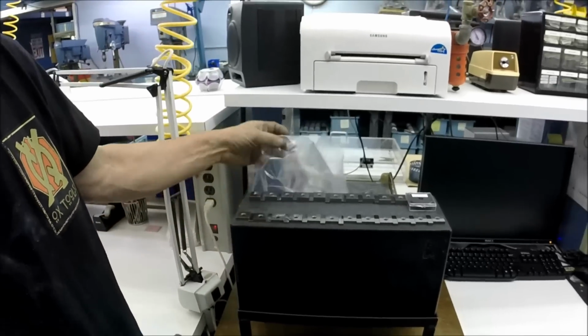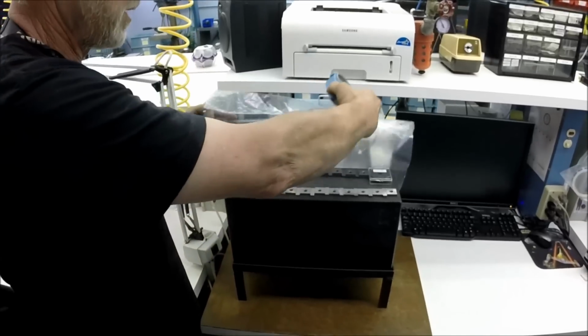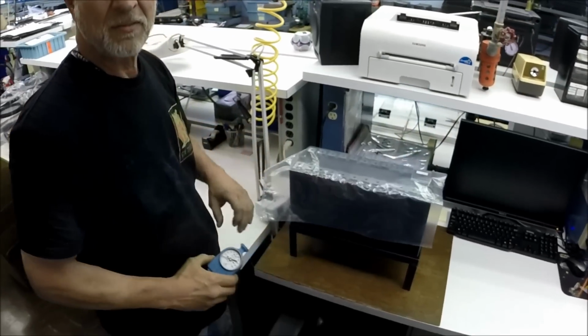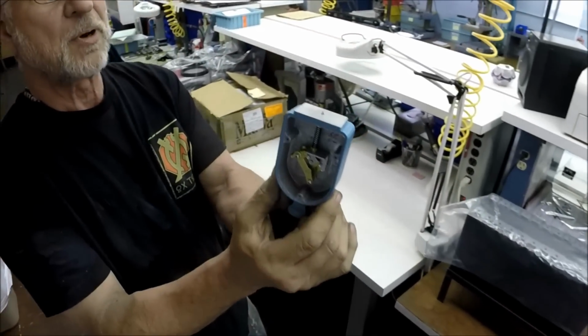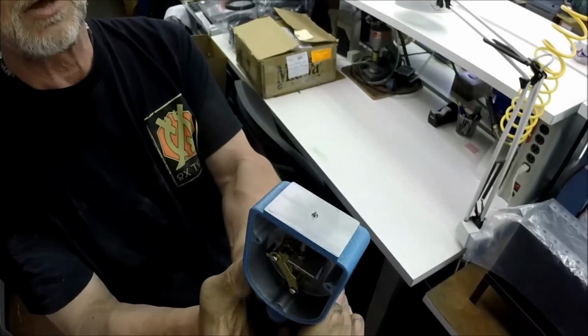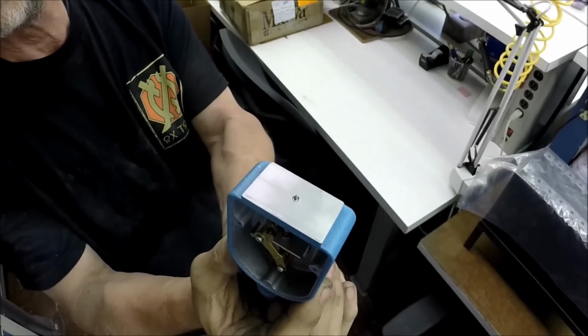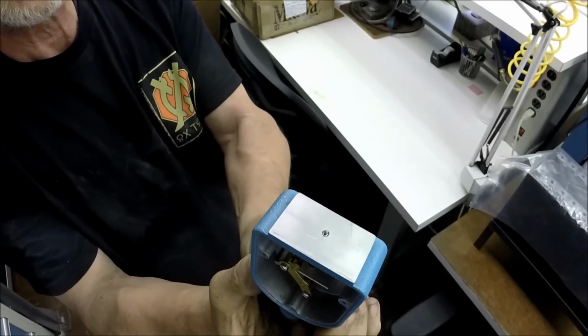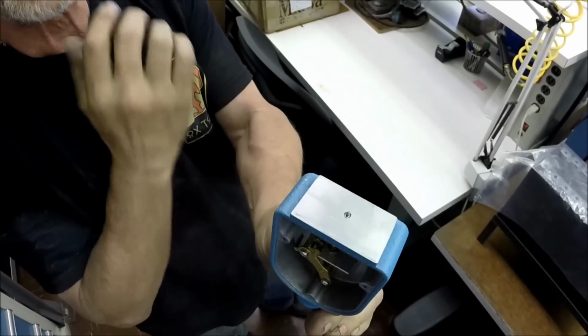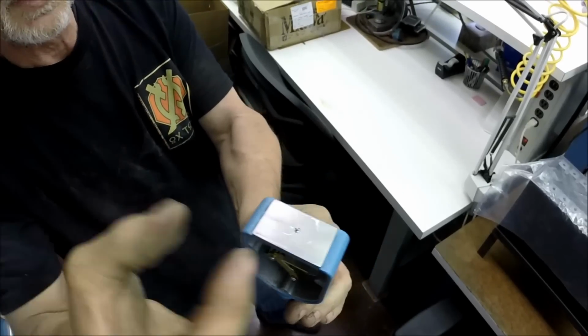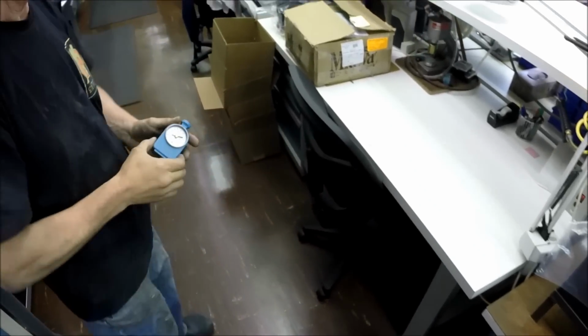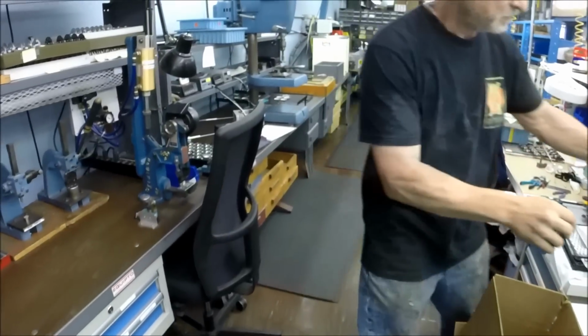For the D-type indenter, you have to use a special device so you don't flatten the tip. The A-type durometer has a truncated cone, and so the tip is not in danger of flattening. But we actually have to hold the D scales on the edge of the cone to keep the pressure from crushing the stone, the tip. This is another instrument we make.